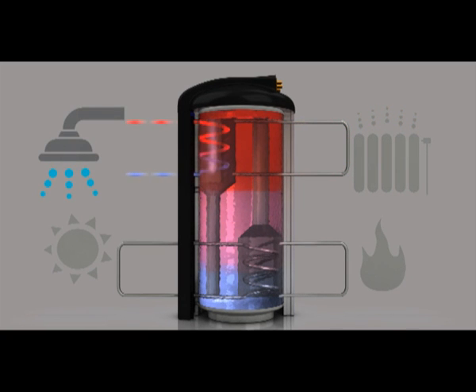In the next case we have hot water consuming. The cold water that comes in is 8 degrees. The water drops and the stratifying pipe is then placing it at the bottom of the tank. All the movement of water is done inside the stratifying pipe and the surrounding water is not moving.